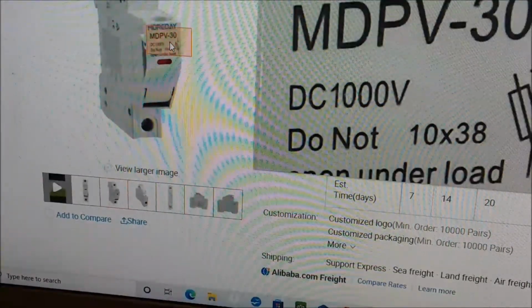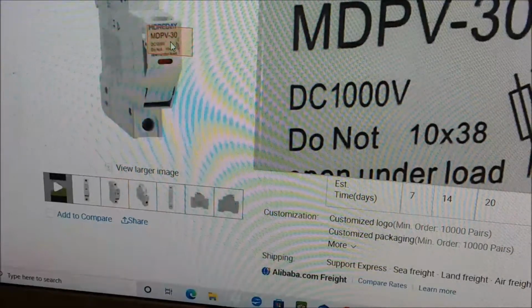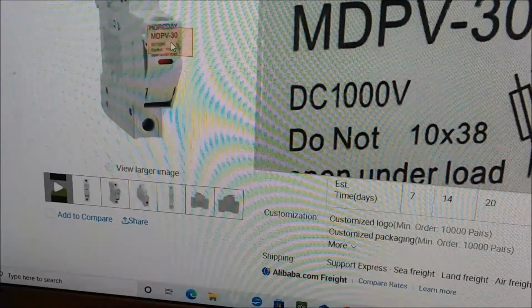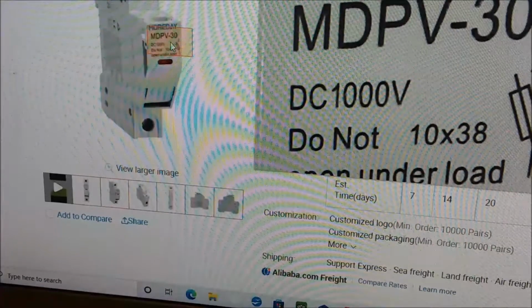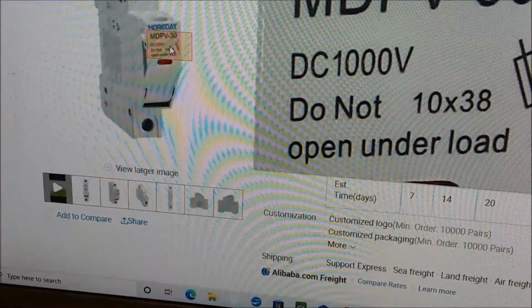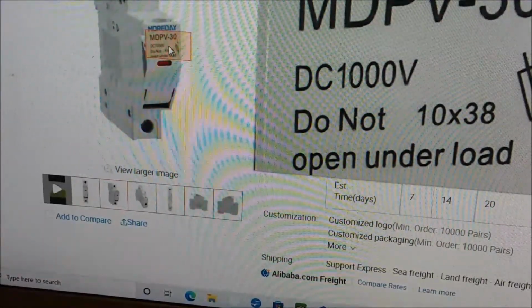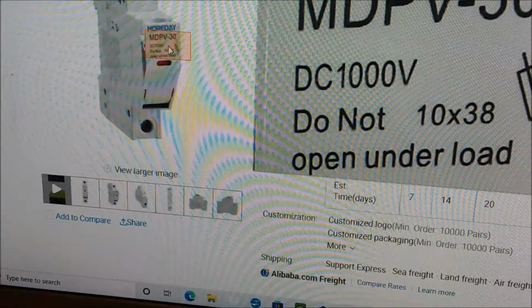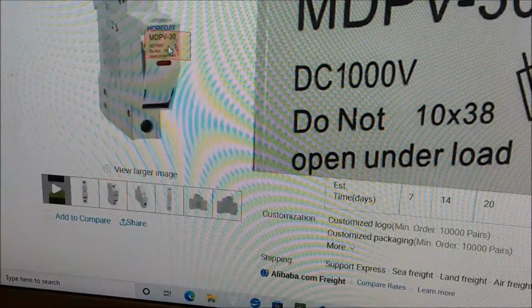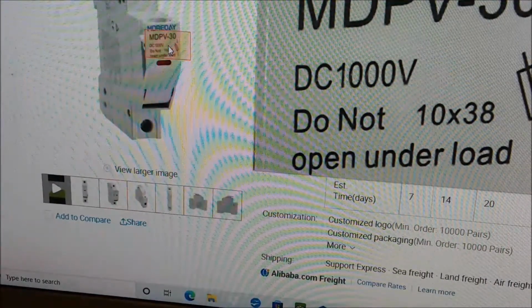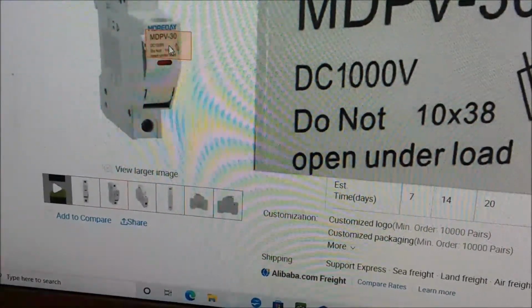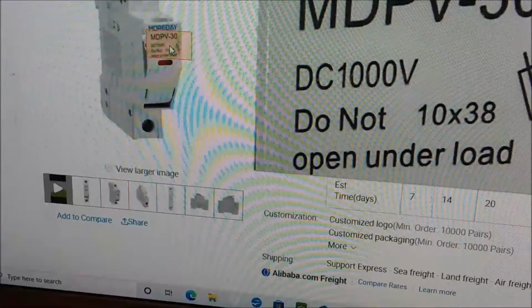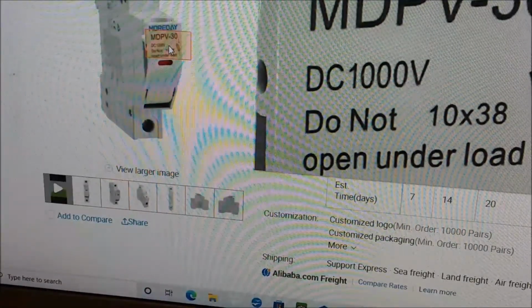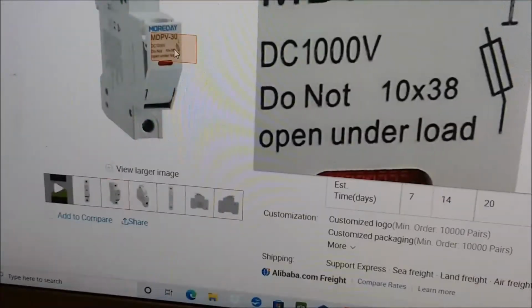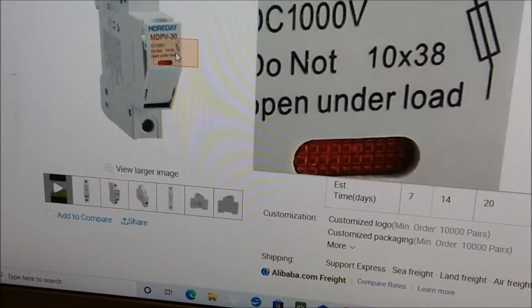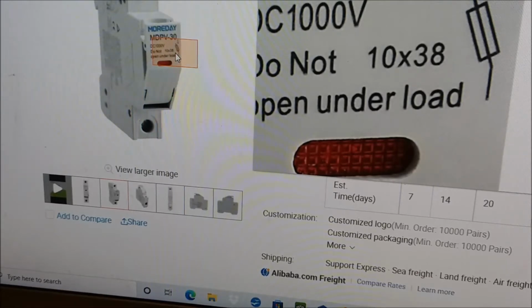This is a 1,000-volt fuse. You can get 1,500-volt fuses, and you can get 600-volt fuses. 600-volt might be a little tight on some solar arrays because your inverter may be able to run up to 550 volts, and some of them are up to 800-volt now, so you don't have a lot of overhead space if you've got a 600-volt rating on your fuse. The 10 by 38, that's the millimeter size of the fuse, diameter and length.